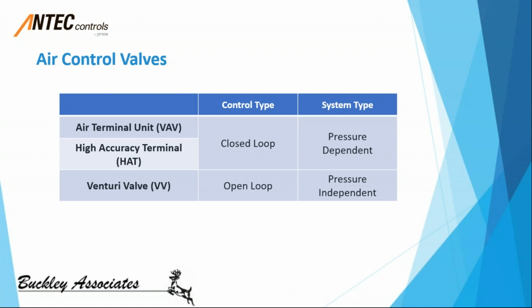Both VAV boxes and high accuracy terminals are very similar in their operation, as they both share closed loop controls and they are both pressure dependent. Venturi valves, on the other hand, operate entirely differently. They have an open control loop and are pressure independent. We're going to define exactly what those two terms mean, but just remember that Venturi valves live in their own world. They operate totally differently than a standard VAV box or a high accuracy terminal. And Venturi valves have many advantages that standard VAV boxes and those high accuracy terminals do not.